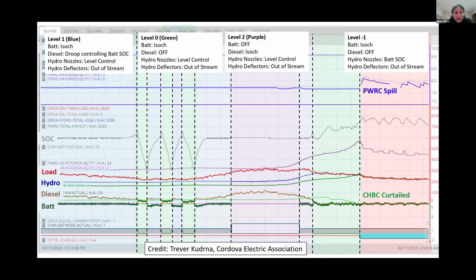So in Cordova CEC's case, depending on the relative amount of load versus hydro, they can be operating in different modes. I'll start with purple in the middle there. When there is much less hydro, they run their diesel in isoch. The hydro has two things that can be controlled: the nozzles, which are slower acting, and the deflectors, which can actually regulate frequency. They don't use them to do that very often right now, but they used to. So when there's not very much water relative to the load, the batteries are off and the diesel's running in isoch. That's level 2 in the middle.